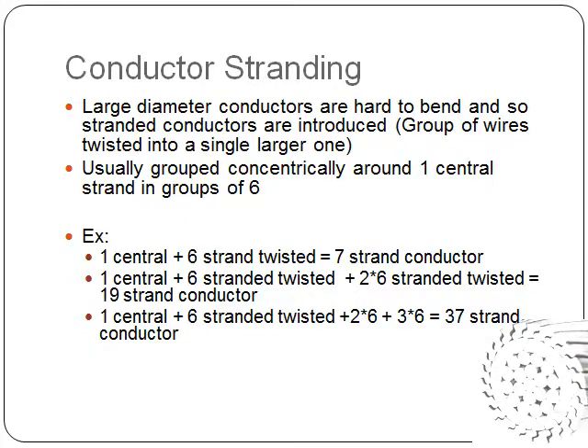Large diameter conductors are very hard to bend, so stranded conductors are introduced — a group of wires twisted into a single large one. They are usually grouped concentrically around one central strand in groups of six. For example, there will be one central strand plus six strands twisted around it, and this is called a seven-strand conductor.